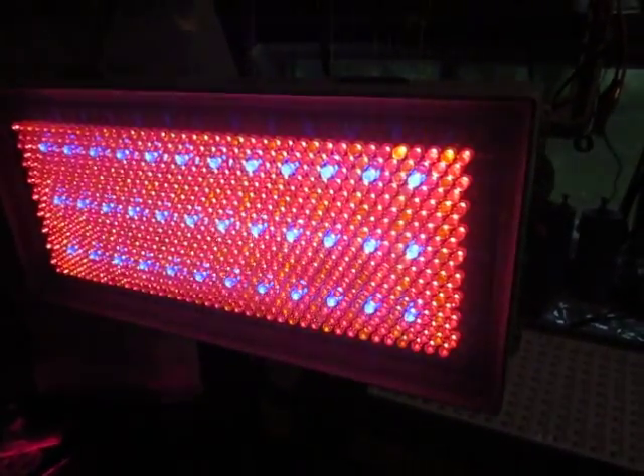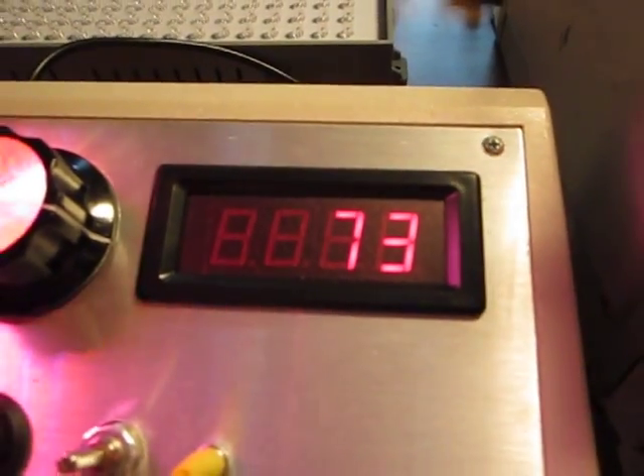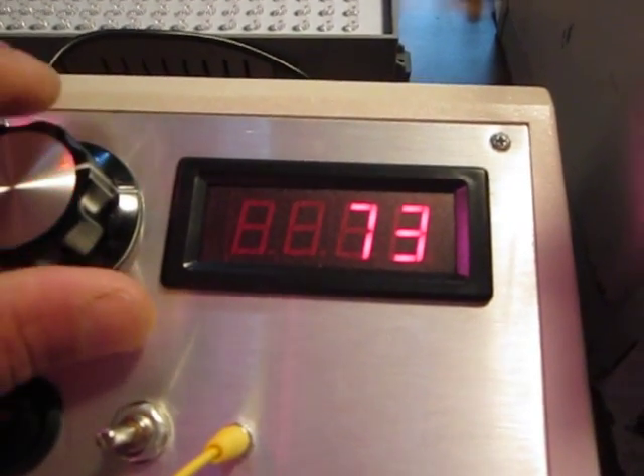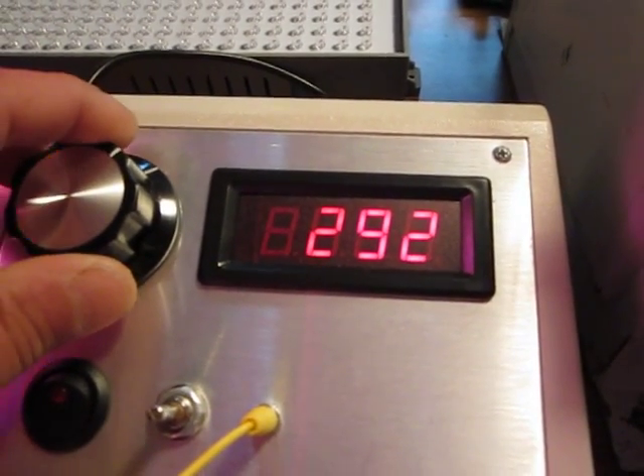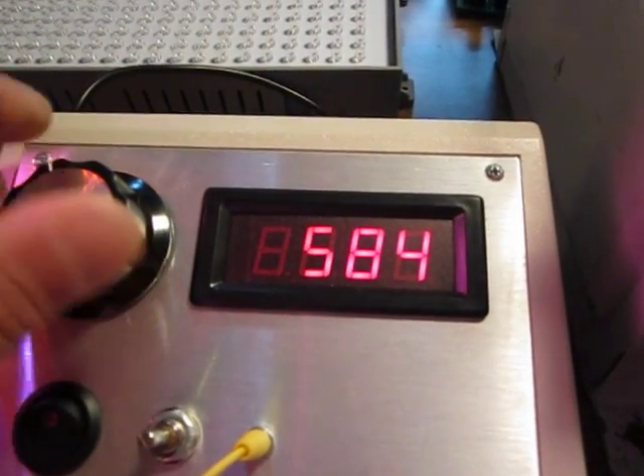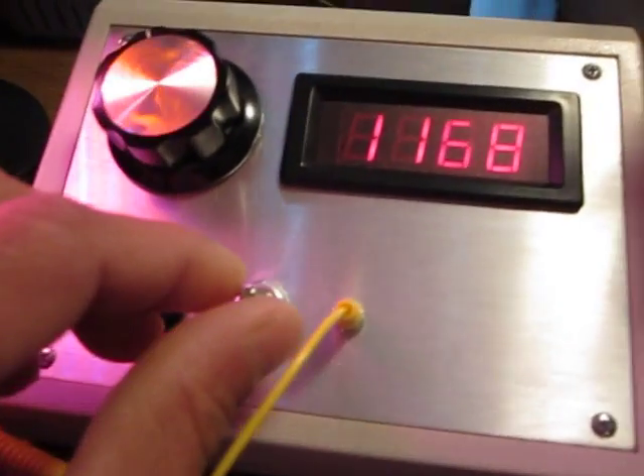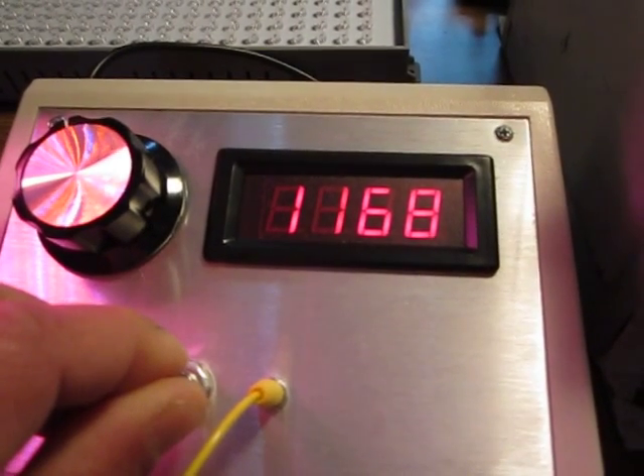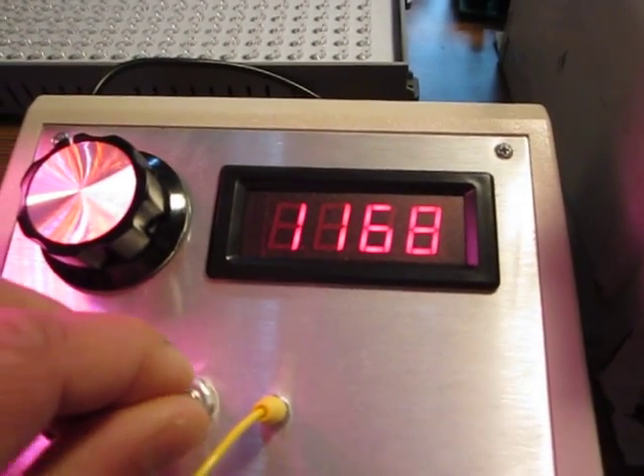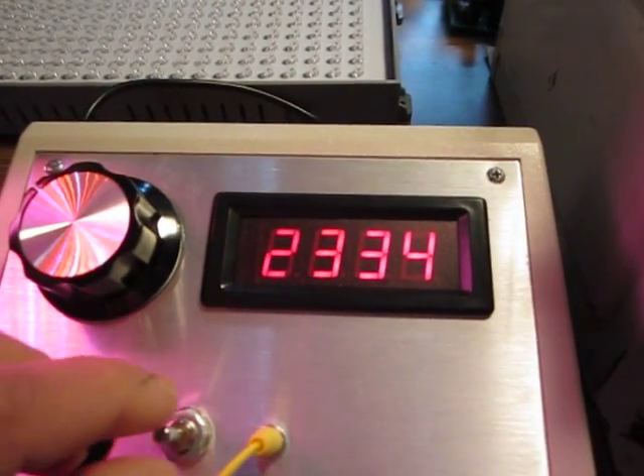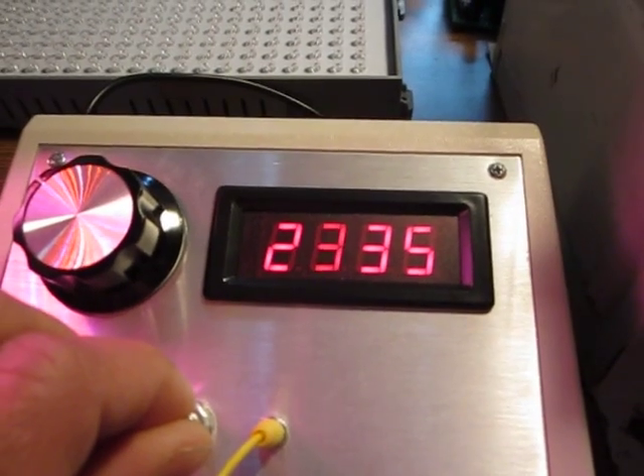I'll show you how this works. You'll see it blinking in the camera. This is the lowest frequency, 73 hertz. That's the effect the camera produces, slightly higher than our eye can detect. Right now we're at 73. We can go up: 146, 292, 584, 1168. When something like that happens, you can turn this down a bit and set it on the right frequency.